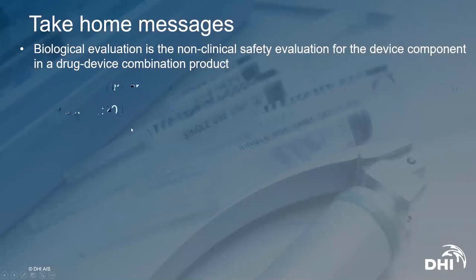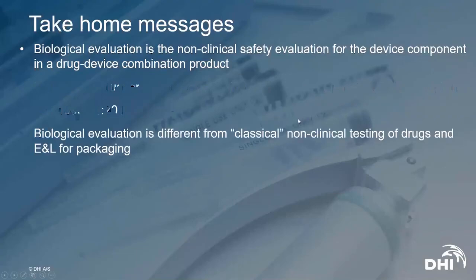ISO 10993 Part 1 from 2018 has not been harmonized yet, not against the MDD and not against the MDR, but it's still considered state of the art. It's recognized by FDA and it's recognized by a number of other authorities around the world. So I would recommend and consider using it, even if it's not harmonized.